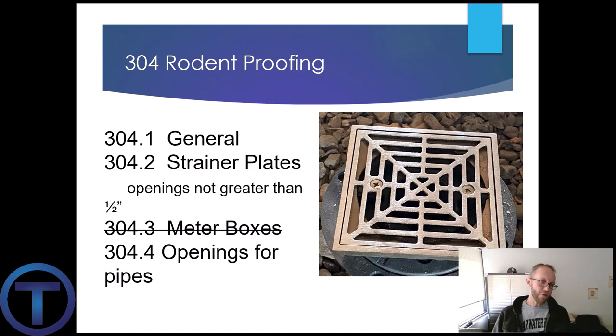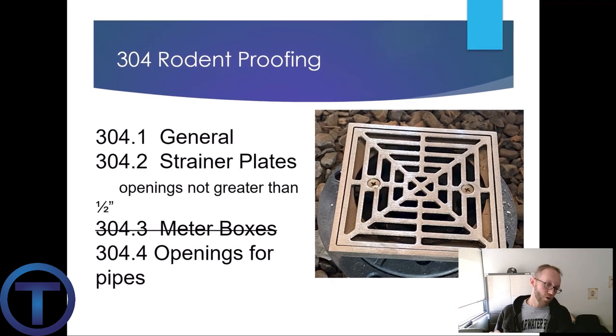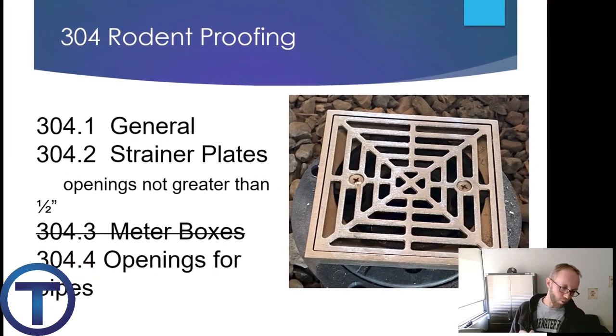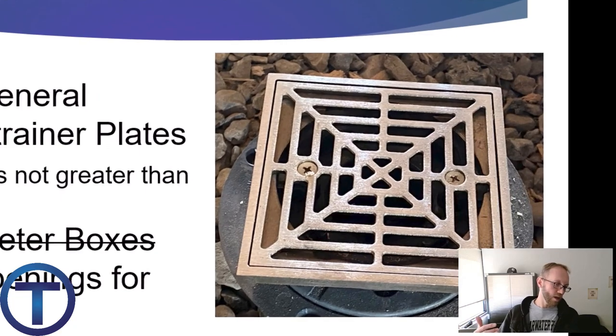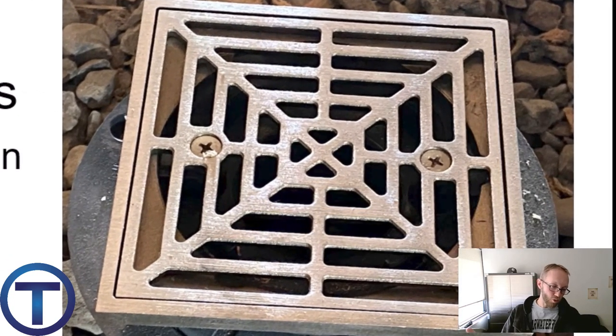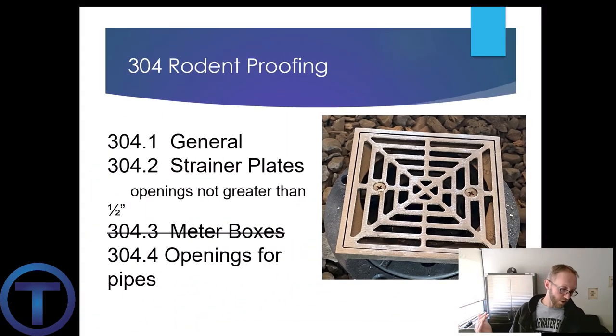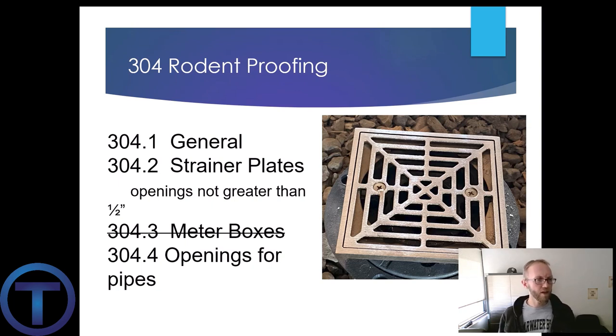304: Rodent proofing. This may not be a huge problem where we live, but in many areas of the world the sewers are rampant with rodents and they will come up your pipes — swim right through the bowl of your toilet. 304.1 says we have to prevent rodents from coming into structures. 304.2: strainer plates on drains or other openings have to have a maximum opening size of half inch. 304.3 regarding meter boxes has been deleted by the Utah amendments — here in Utah we don't even have meter boxes, so you can put a line through that section.